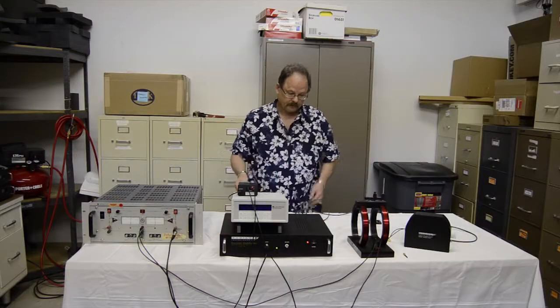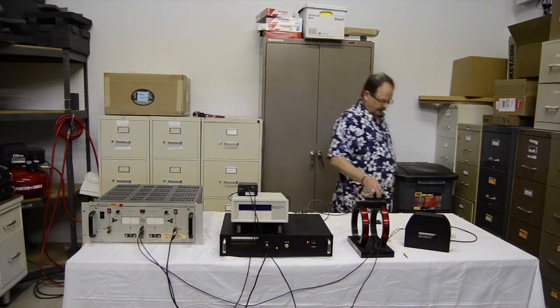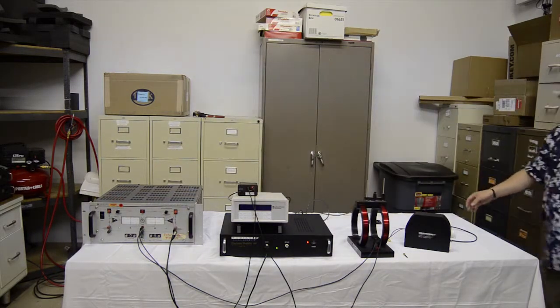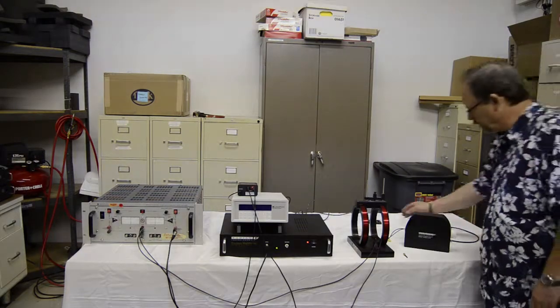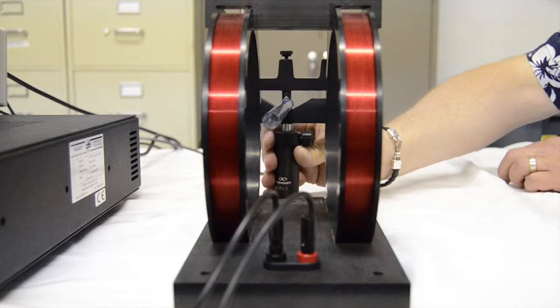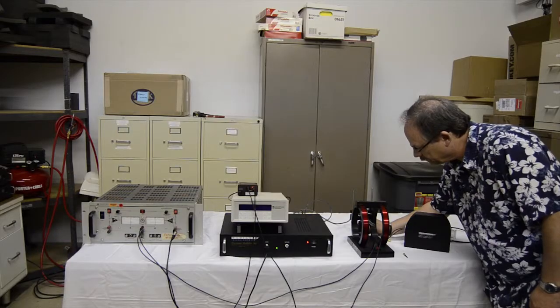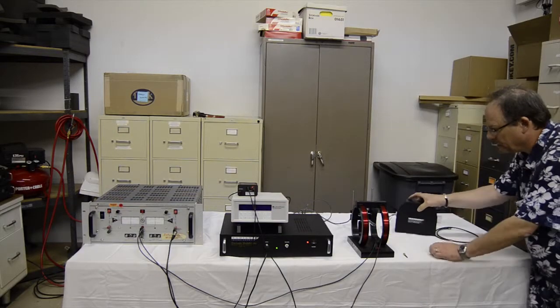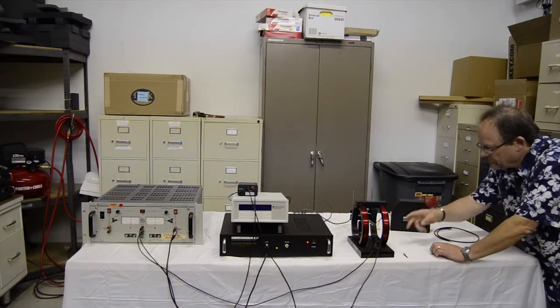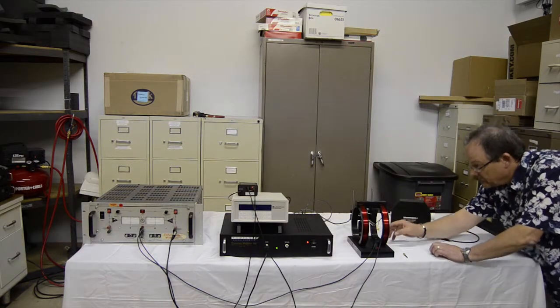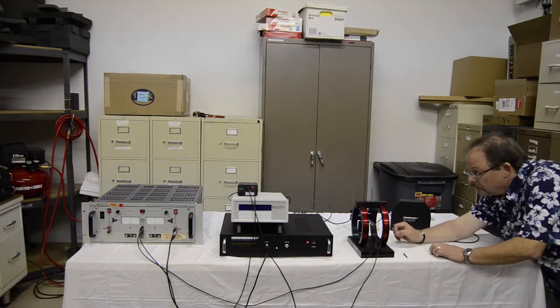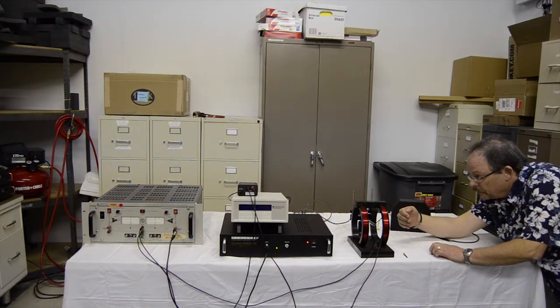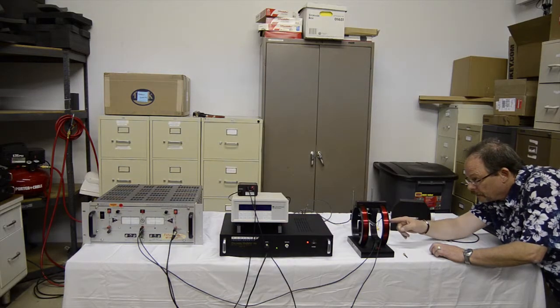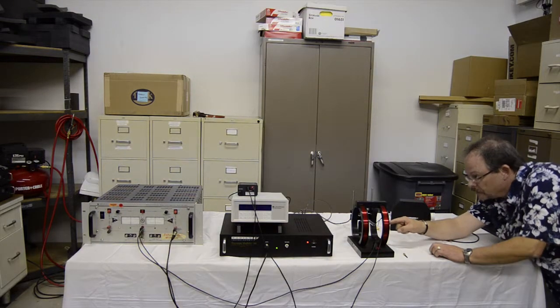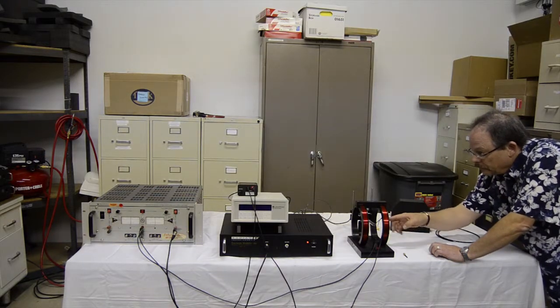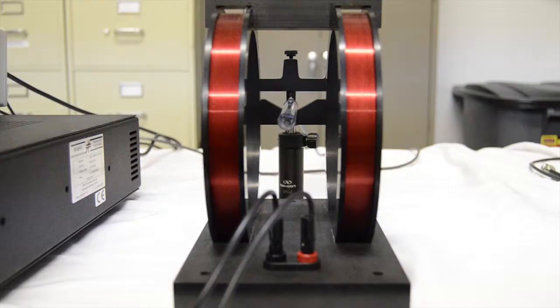Finally, to make the measurement, I need to insert the wand into the Helmholtz coil to detect the exact field being generated by the input current. When I insert the wand, first of all, I make sure that it's vertically and horizontally centered within the coil, and I also make sure that the face of the detection surface of the wand is perpendicular to the direction of the field, which is through the center of both coils.